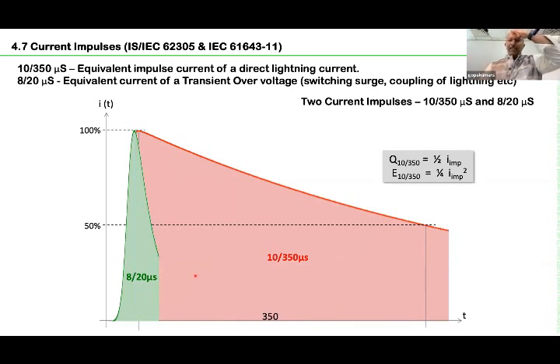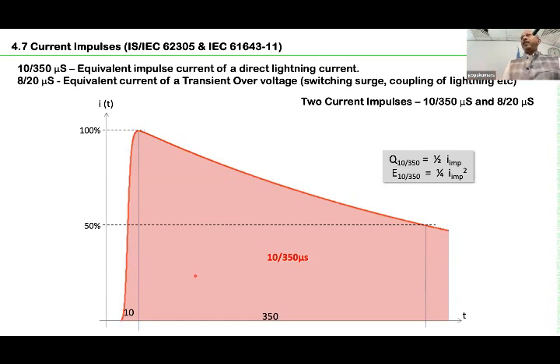The first one is called 10/350 microseconds, which is the energy equivalent of a partial lightning current, direct or partial lightning current. Partial lightning current means that of the whole lightning current created by a direct lightning strike, a part of it is going to flow through the SPD. The energy equivalent of lightning current is termed 10/350 microseconds, which means the current goes from 0 to peak in 10 microseconds and comes to half value in 350 microseconds, as you can see here.